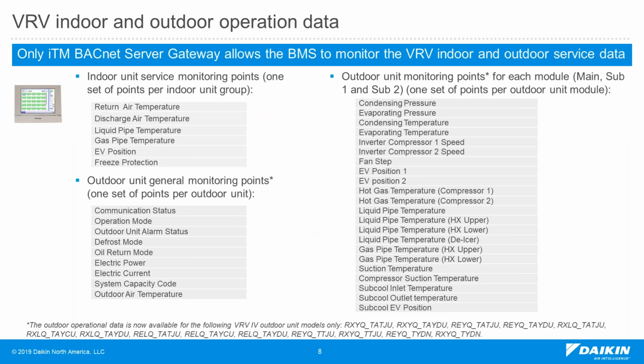The ITM gateway has another advantage against the hardware BACnet gateway, which is that it provides the VRV indoor unit and outdoor unit operational data. So with this operational data, the BMS can monitor and trend the entire mechanical system. For each indoor unit, it provides 6 service monitoring data points, 1 set of these points per indoor unit group. For each outdoor unit, it provides 1 set of general monitoring points, and it also provides 1 set of module monitoring points for each module in that particular outdoor unit.